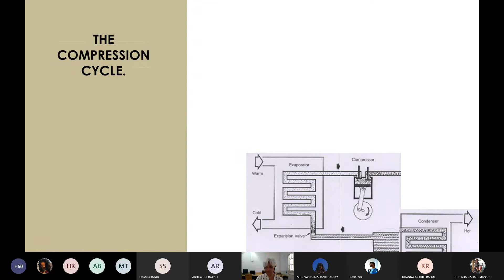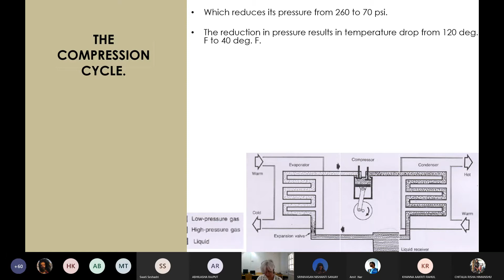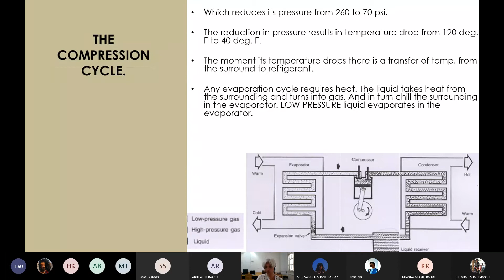Same diagram, more explanation. Now we go to the evaporator, which I've already explained. Quickly read this. The reduction in pressure results in the temperature drop from 120 to 40 degrees. The moment its temperature drops, there is a transfer of heat from the surroundings to the refrigerant. Any evaporation cycle requires heat. The liquid takes heat from the surroundings and turns into gas, and in turn chills the surroundings. The chilling can happen through water or through air. So low pressure liquid evaporates in the evaporator and the cycle continues.